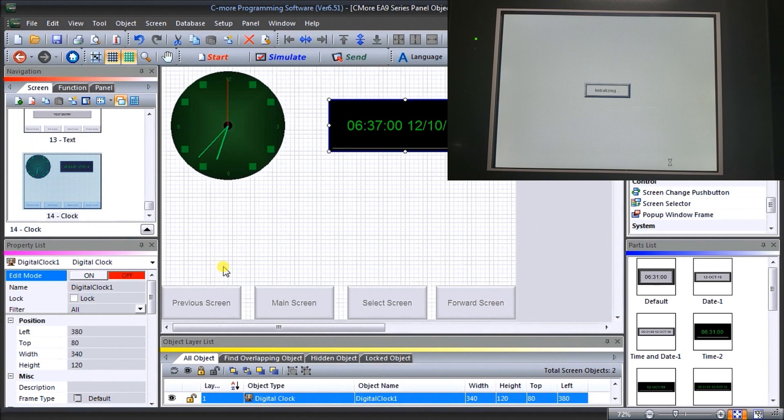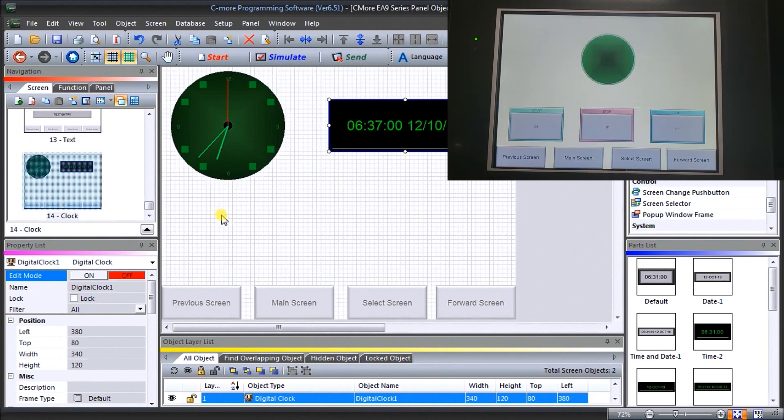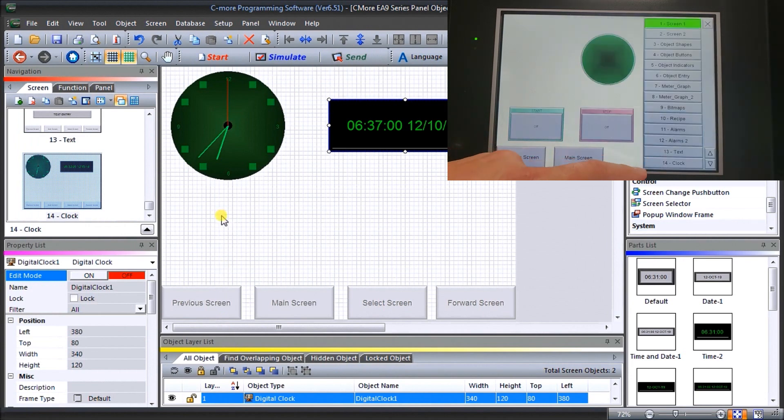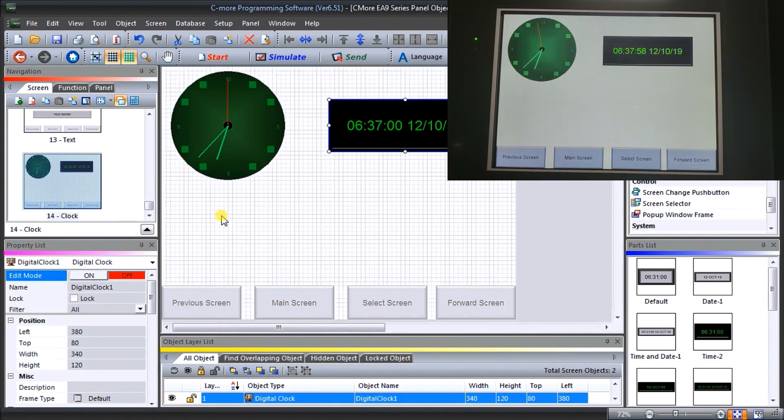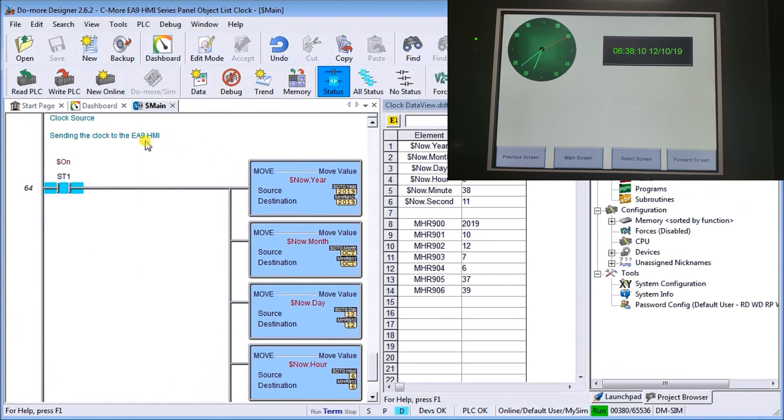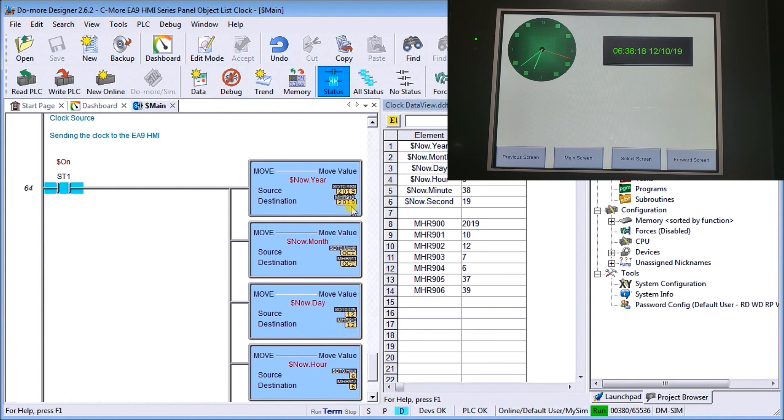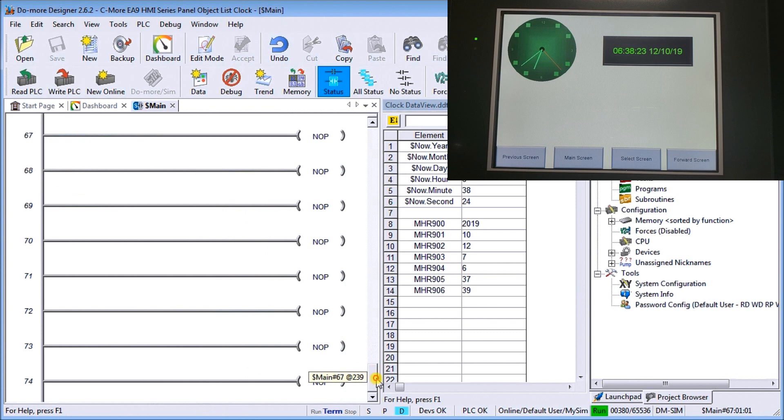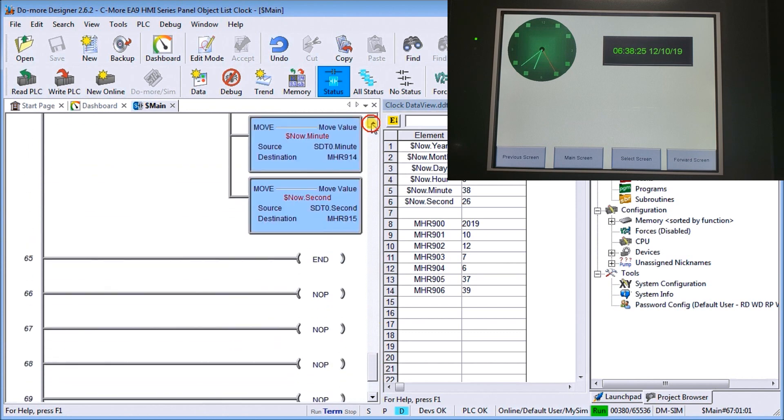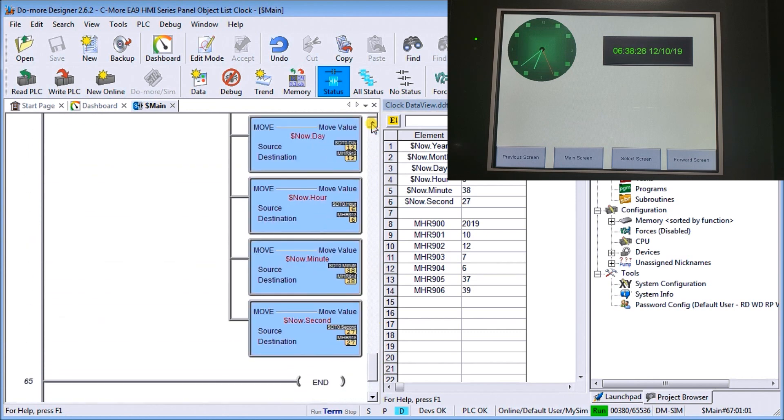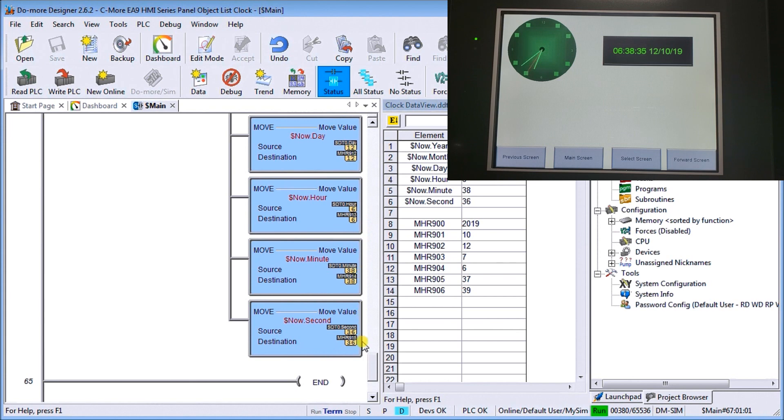Hit OK, close this. Now what you'll see is if we call up our screen, select our clock, our clock is now updating but updating with our values that are in our PLC. If we look at our PLC again, you'll see that here what I'm doing is I'm moving the real time clock - the year, month, and date - into MHR 910, 911, and 912. Then we have the hour, minute, and second, and these are being put into MHR 913, 914, and 915.